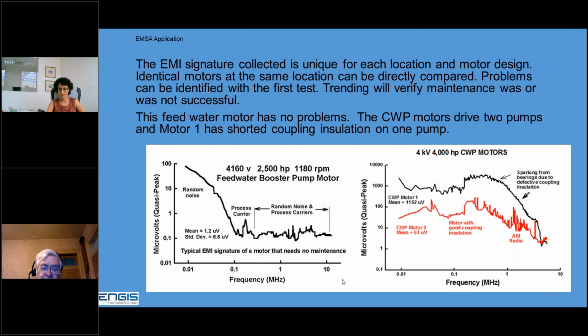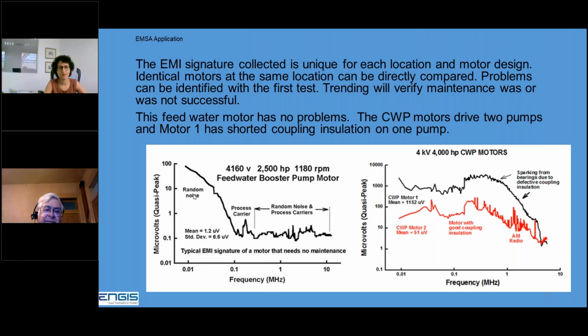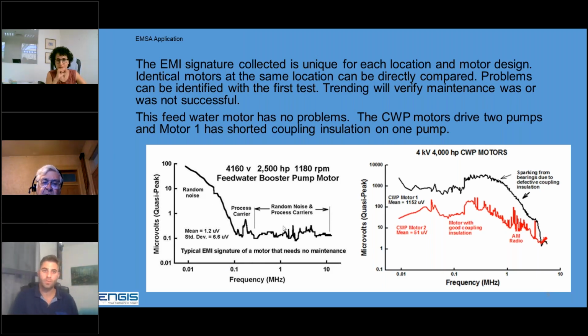The horizontal scale is the frequency. So this is 10 kilohertz, 100 kilohertz, 1 megahertz, 10 megahertz. So it's an amplitude versus frequency plot. When you collect this data, you go back and look at the videos at various frequencies and you determine what this is. So in this case, where it was high here was random noise. This is a process carrier in that plant, and then also random noise and carriers here. This is almost the noise floor of the equipment, 0.1 microvolt. So you can see it's extremely sensitive. There's nothing wrong with this motor. It's in good shape.